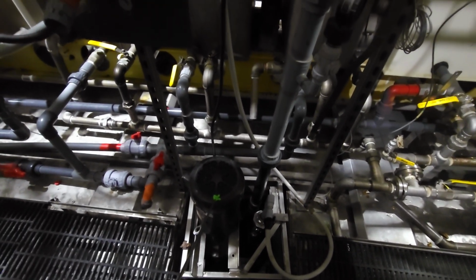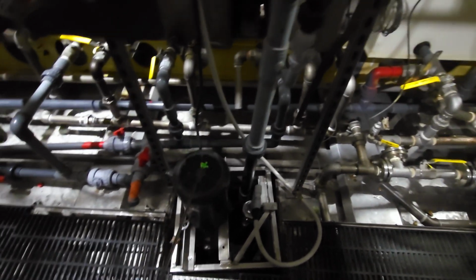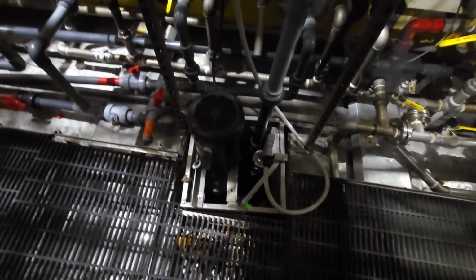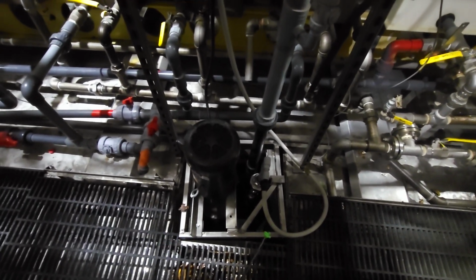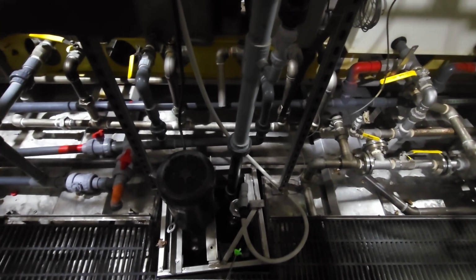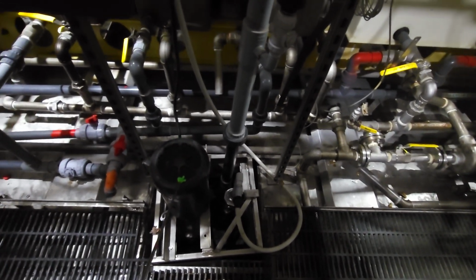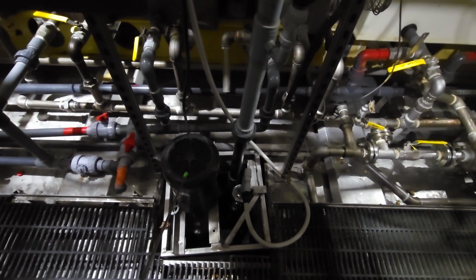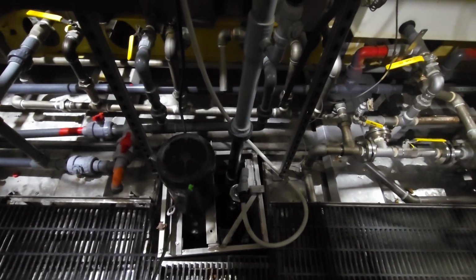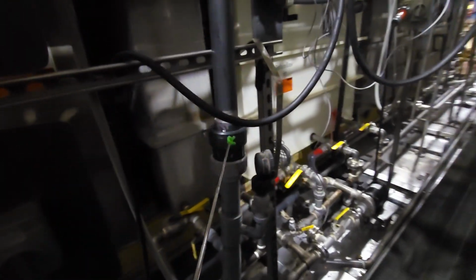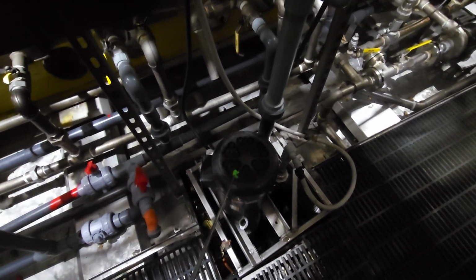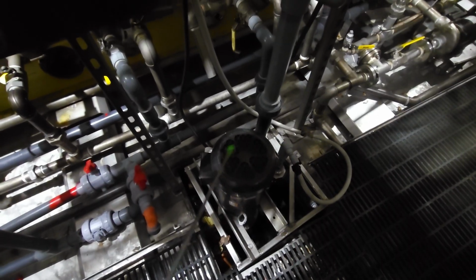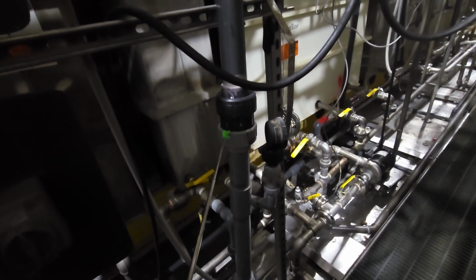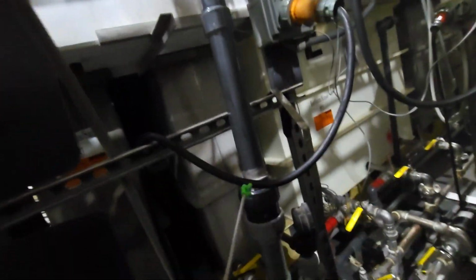Troubleshooting. Say no flow alarm. First thing you do, come back and just look. You got water in your pit? Because if you ain't pumping water out, your pit's going to be overflowed. Obviously, that means your pump's not working. Alright. Say you're looking on your SCADA and it's running too much. Okay, now most likely going to be caused is your check valve is going to be stuck open. So as it fills up, it'll backfill. A good way to know is watch your fan blades. If you see them fan blades stop and they start spinning backwards, your check valve's not working or your valve's closed. Make sure of that.